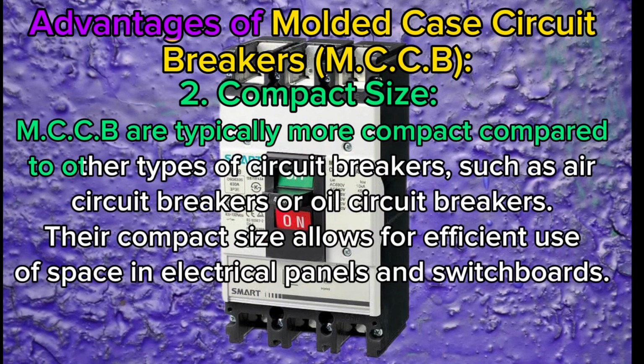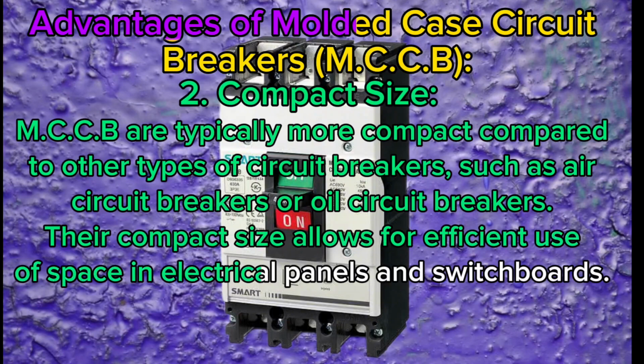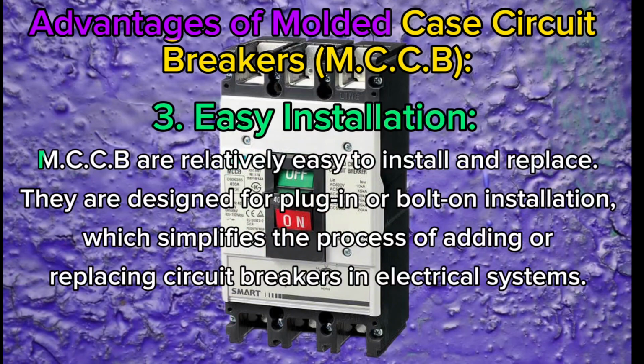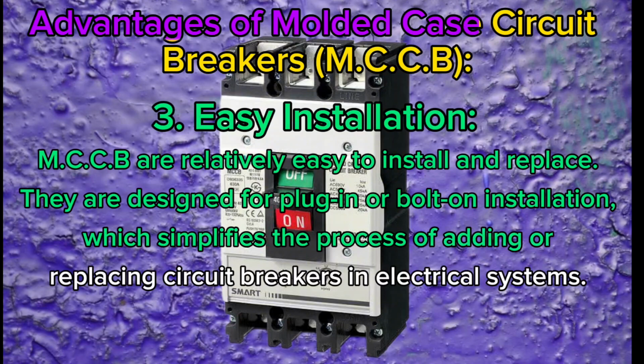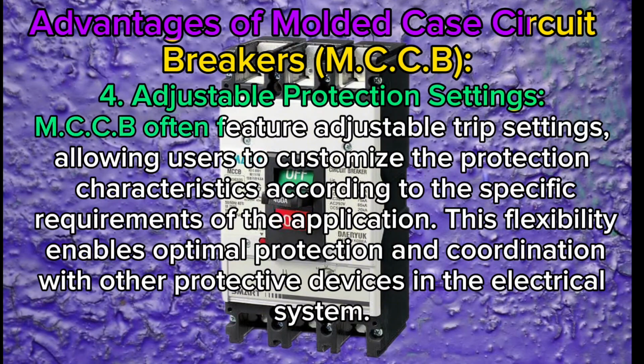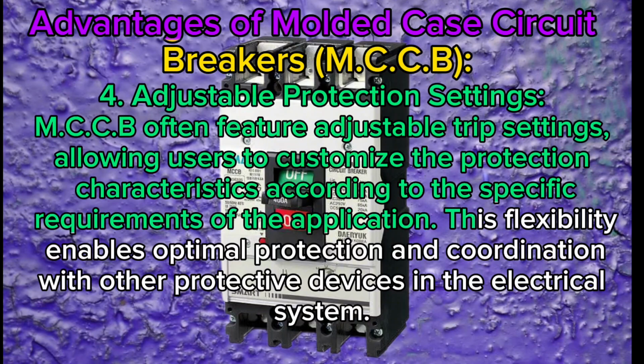MCCBs are typically more compact compared to other types of circuit breakers such as air circuit breakers or oil circuit breakers. Their compact size allows for efficient use of space in electrical panels and switchboards. 3. Easy installation. MCCBs are relatively easy to install and replace. They are designed for plug-in or bolt-on installation, which simplifies the process of adding or replacing circuit breakers in electrical systems. 4. Adjustable protection settings. MCCBs often feature adjustable trip settings, allowing users to customize the protection characteristics according to the specific requirements of the application. This flexibility enables optimal protection and coordination with other protective devices in the electrical system.